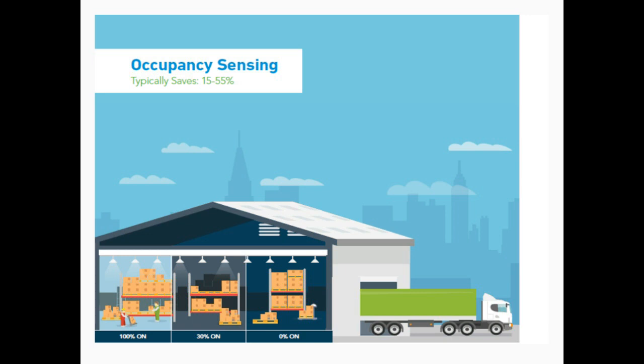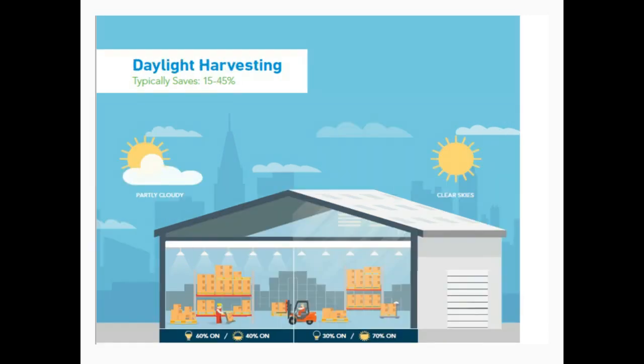If daylight is available, why use artificial light? That's an important question when it comes to the next strategy: daylight harvesting. Basically, daylight harvesting automatically regulates the use of your electric lighting in response to the amount of daylight available. So say you want to keep 30 foot candles in your area. The sensor reads the amount of natural light coming into the space and adjusts the electric lighting to maintain the 30 foot candles at all times.